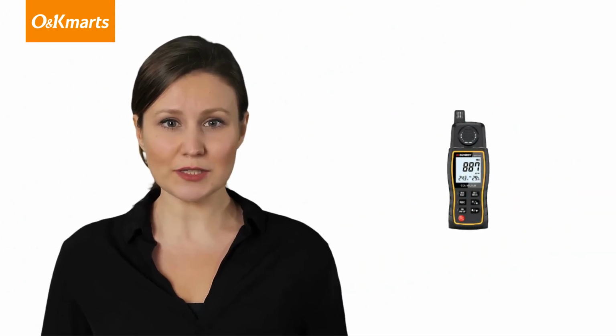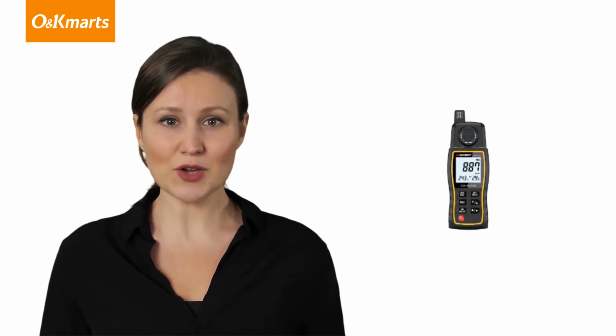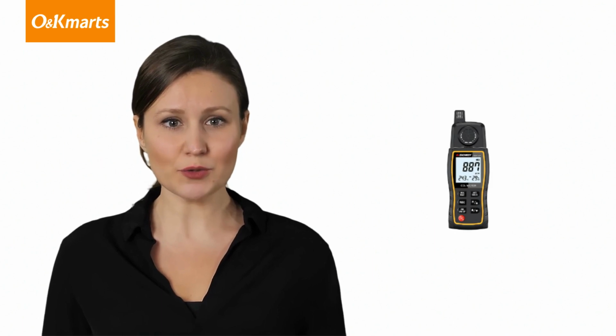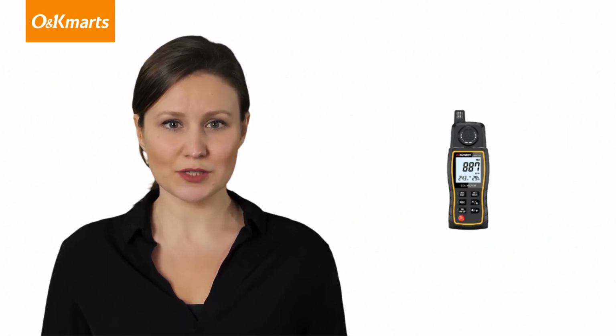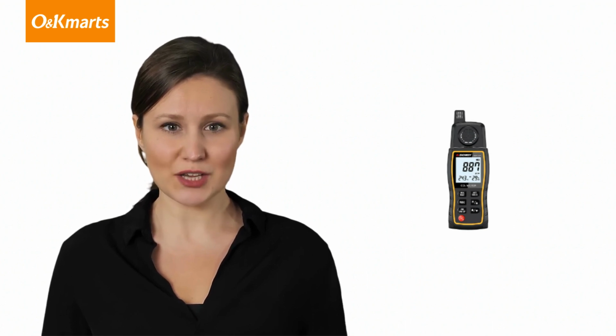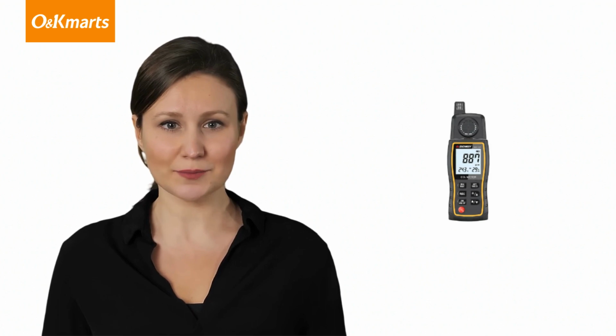According to their working principles and application areas, carbon dioxide, CO2, detectors can be divided into several types. Chemical absorption CO2 detectors. These detectors use chemical absorbents, such as barium hydroxide, to absorb CO2 in the air and detect the presence of CO2 by observing the color change or volume change of the absorbent. This type of detector is usually used for simple visual detection, such as color change indication.